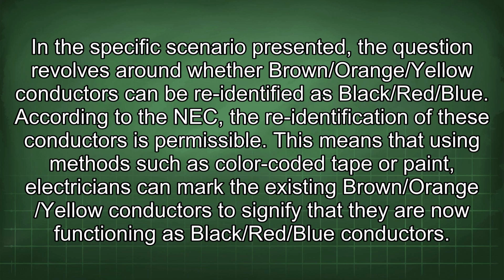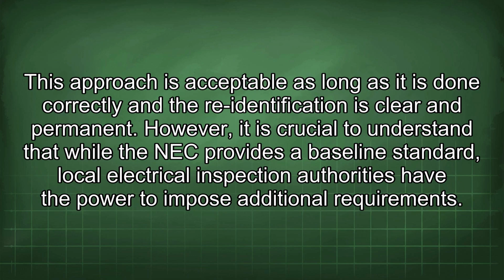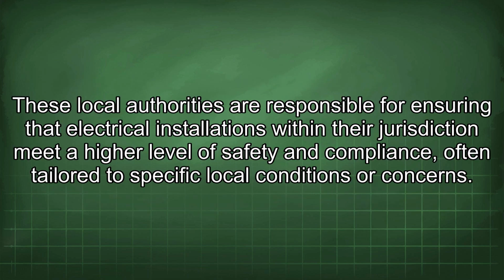This means that using methods such as color-coded tape or paint, electricians can mark the existing brown/orange/yellow conductors to signify that they are now functioning as black/red/blue conductors. This approach is acceptable as long as it is done correctly and the re-identification is clear and permanent. However, it is crucial to understand that while the NEC provides a baseline standard, local electrical inspection authorities have the power to impose additional requirements. These local authorities are responsible for ensuring that electrical installations within their jurisdiction meet a higher level of safety and compliance, often tailored to specific local conditions or concerns.